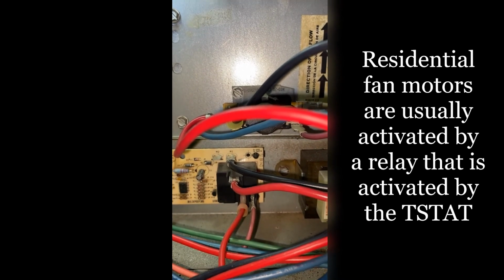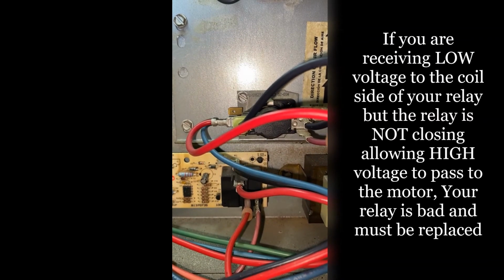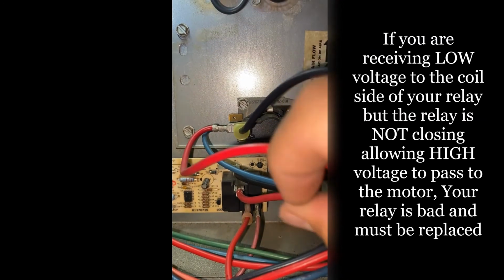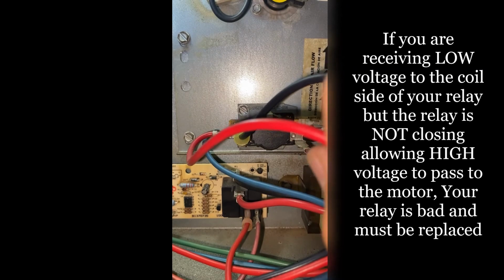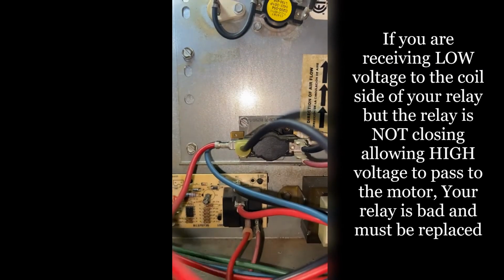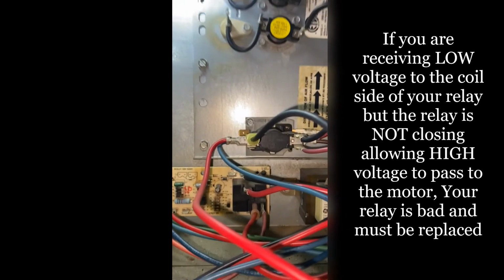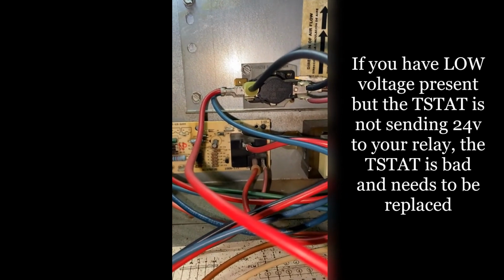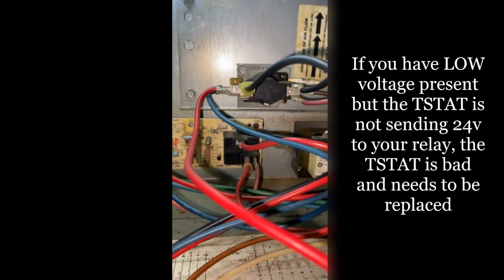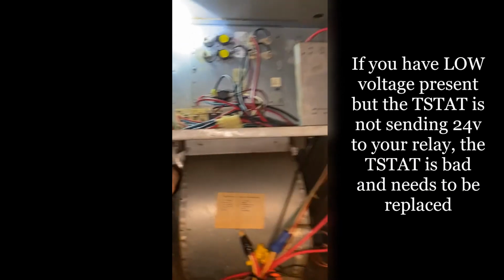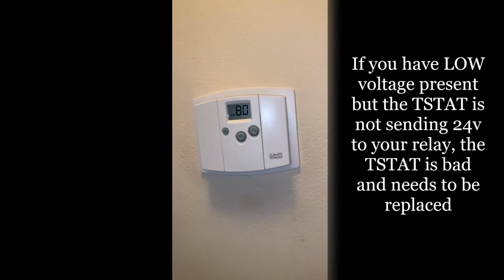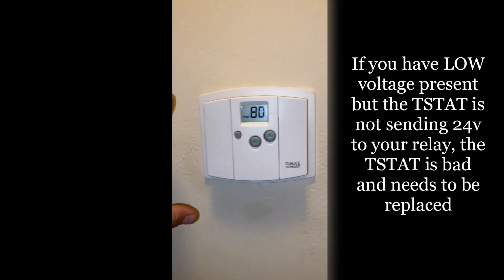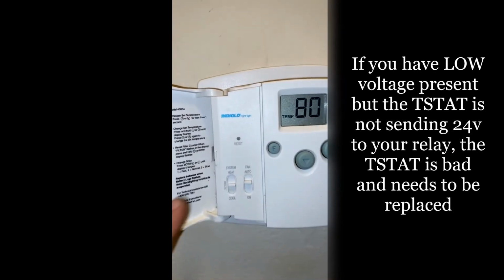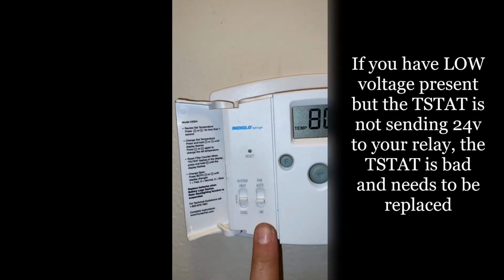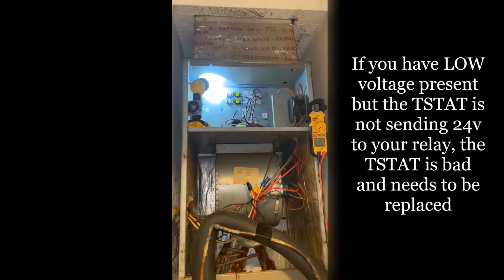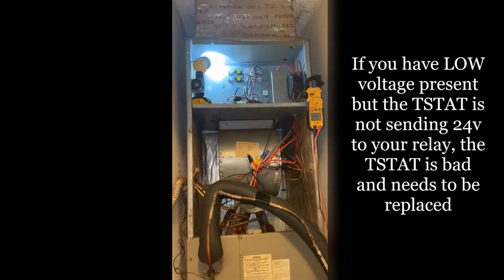I have videos on relays too, and contactors. You have to be getting control voltage to your relay at the terminals, and if the relay's not closing, the relay's bad. So what if you have your high voltage and low voltage, but you're not getting control voltage to your relay? What's supposed to send control voltage to your relay is your thermostat. So if you have that thermostat on the on position and you're not getting voltage to your relay, your thermostat is bad and needs to be replaced.